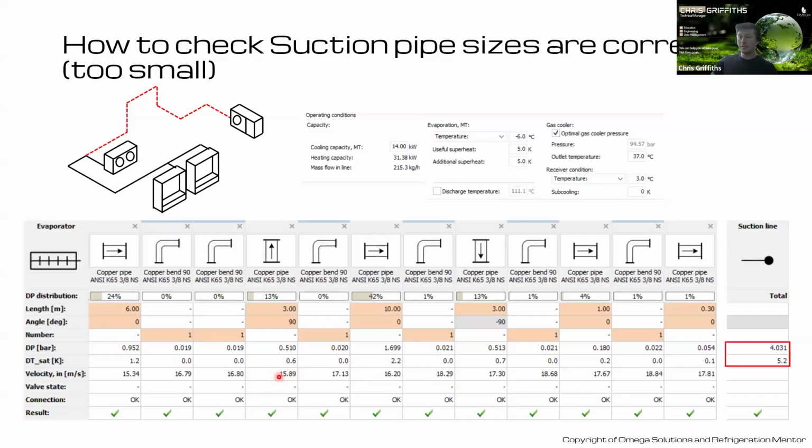So we'll have a look at this. For a velocity for a riser, I'd say that's okay. Then we look at the overall pressure drop through the rest of it, and we've got 0.6 Kelvin there just in our riser. It's a fairly high pressure drop, but it's only a small section. It's a 3-meter riser, or 10 foot. That's okay. What about the rest of it though?